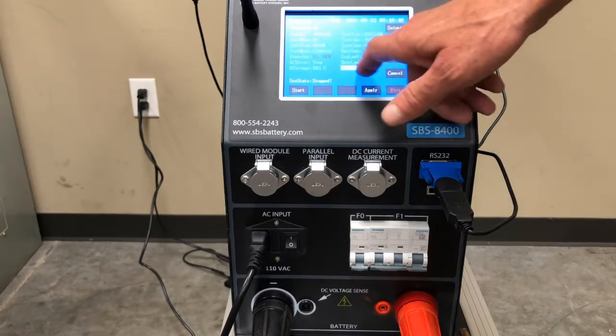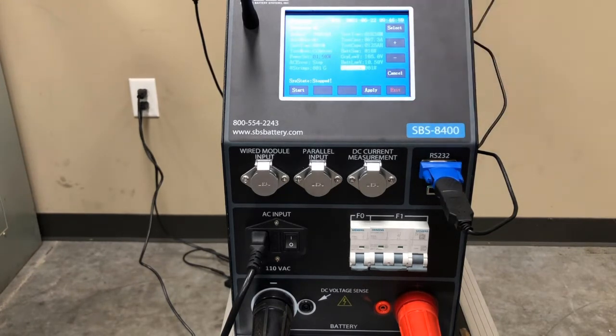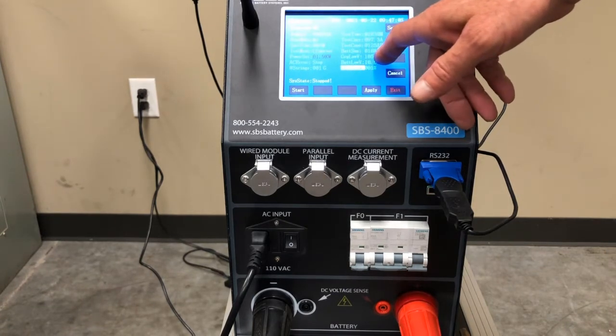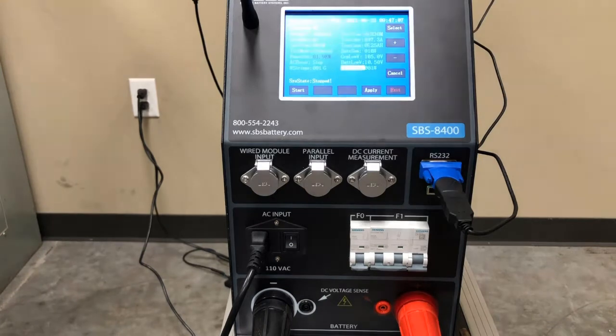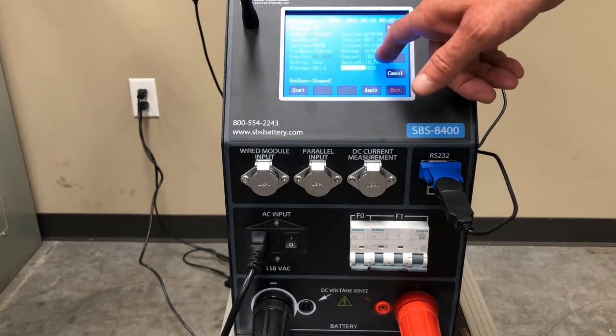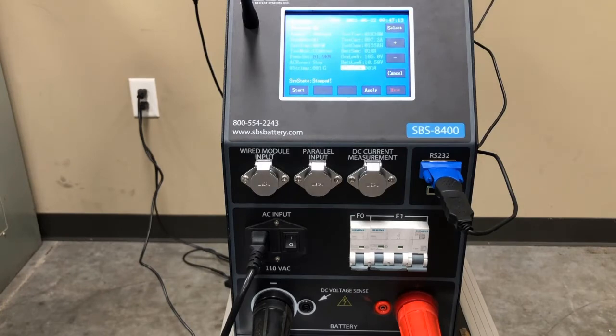So I usually set number of battery lows to 4 if I'm doing 12-volt block batteries, and I'll set it to 6 or 8 if I'm doing individual 2-volt cells. That way a number of cells can come down below that target value. As long as my group voltage is still above that 105, I want the test to continue to run until that 105 is the only parameter that shuts my test down.